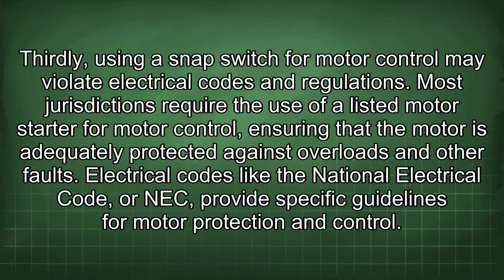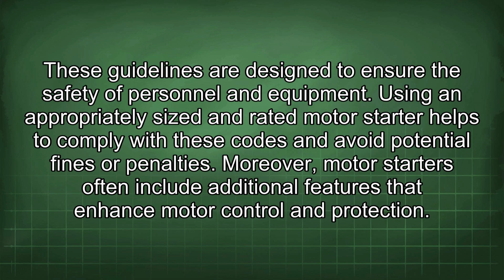Thirdly, using a snap switch for motor control may violate electrical codes and regulations. Most jurisdictions require the use of a listed motor starter for motor control, ensuring that the motor is adequately protected against overloads and other faults. Electrical codes like the National Electrical Code, or NEC, provide specific guidelines for motor protection and control. These guidelines are designed to ensure the safety of personnel and equipment. Using an appropriately sized and rated motor starter helps to comply with these codes and avoid potential fines or penalties.